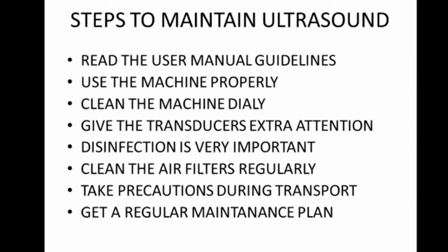You have to clean the probes, keyboards and the trackball on a regular basis with tissue, because sometimes dust will go inside and start giving speckles in the image. It will start producing white lines, and then white dots in the image. These are a few things that you can avoid if you clean the machine daily.